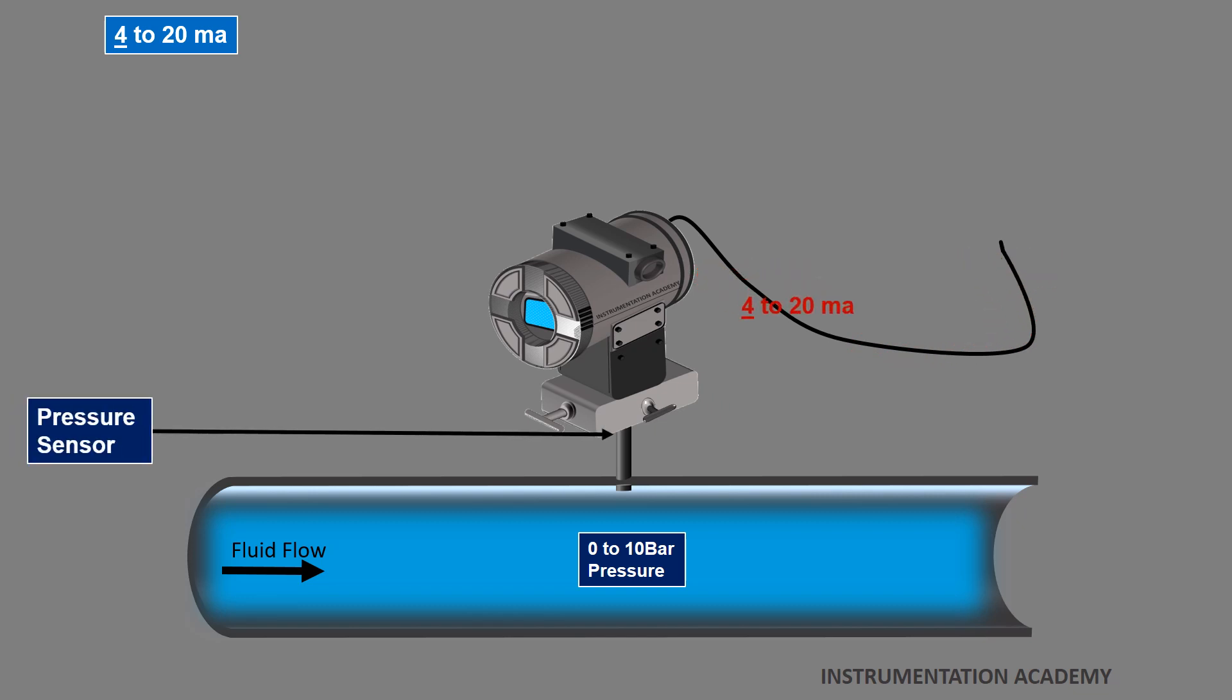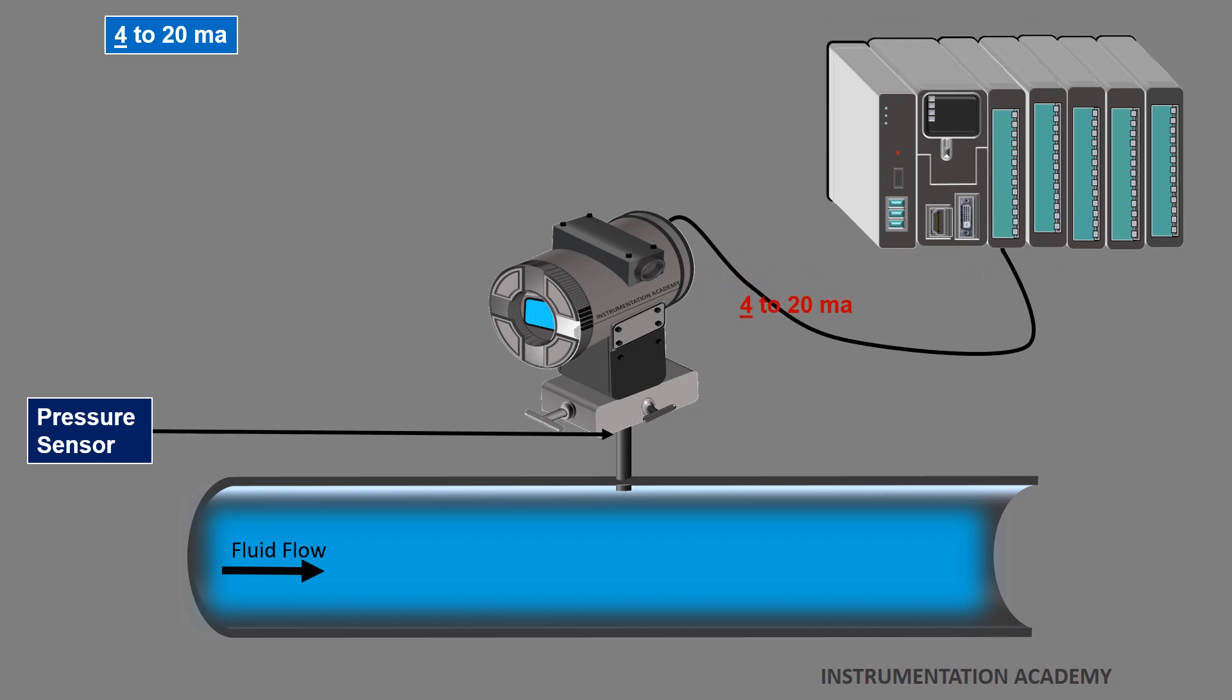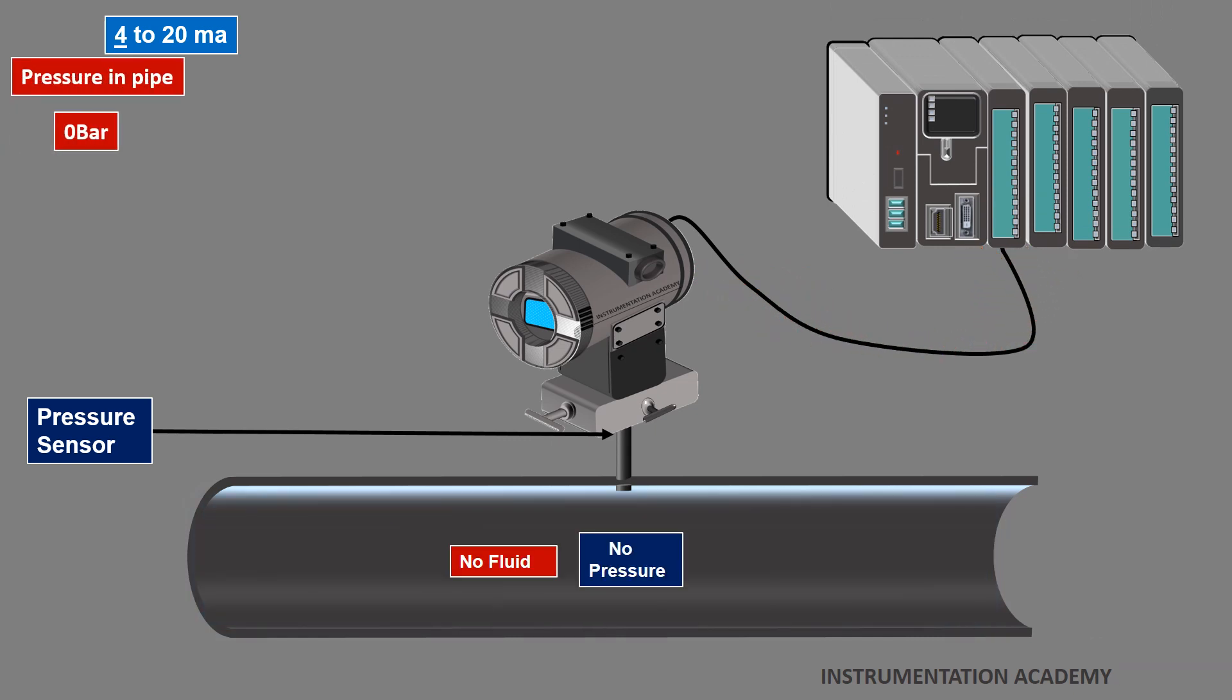This pressure transmitter is connected to input card of a PLC. When there is no fluid flowing through the pipeline, no pressure is exerted on the sensor. But the pressure transmitter still generates 4 mA current signal at the output terminal.